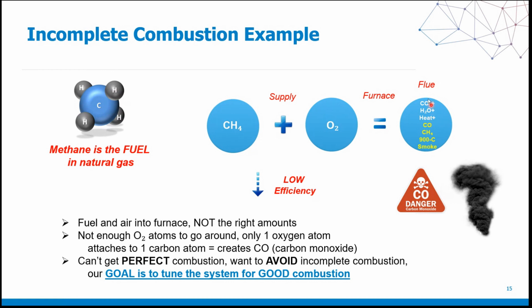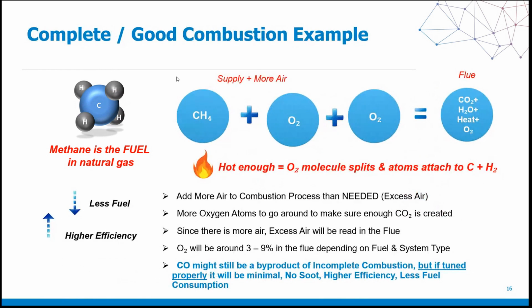What do we have in our flue? High levels of CO, as you see here, and high levels of the unburned fuel, which in this case is natural gas or methane. So what do we have? We have an inefficiency that we've created with the appliance, and we're also producing high temperatures and smoke. So knowing this now and what incomplete combustion looks like, we can now look to migrate ourselves over to complete. And what does that look like?